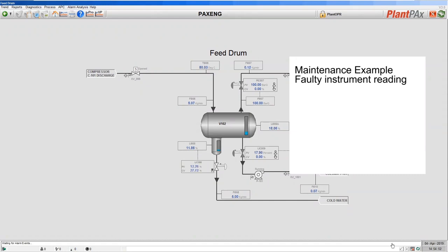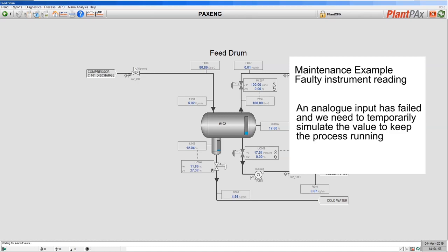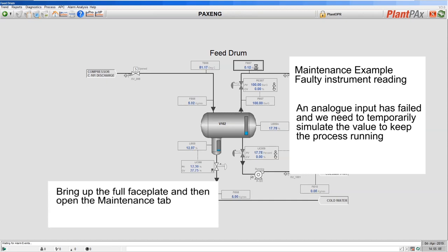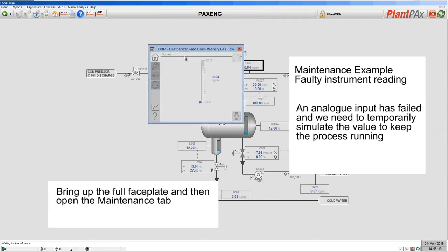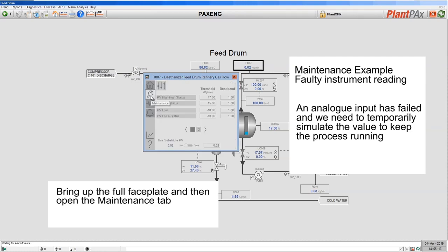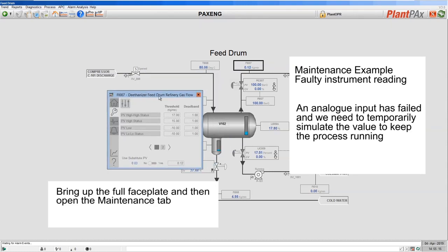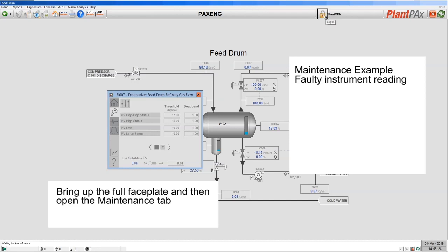Now let's look at the substitute feature that's built into the library as standard. Let's say that our analog input has failed at the top of our feed drum and we need to simulate a value to allow us to complete our process production run. I can do that by bringing up the full faceplate and going to the maintenance tab. Because of security, as a logged-in operator I don't have the ability to substitute the analog input, so I need to log in as a higher-level user.